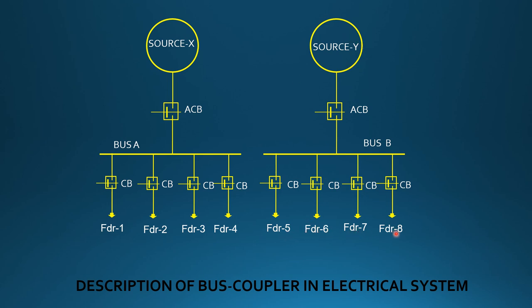As a result, two sources of supply are kept ready to cater the load. Two sources may be used individually or one of the sources may be kept standby. When any of them is kept standby, the bus coupler is used to extend power from any source to feed both loads by making both sources A and B couple.